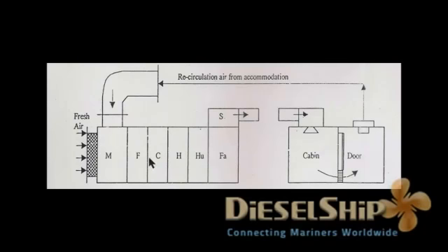The air flowing over the cold coils gets reduced in temperature depending on the setting. So let's say we want 20 degrees at the air handling unit outlet. When we set so, the expansion valve opens accordingly, and when 20 degrees is reached, the compressor cuts off.